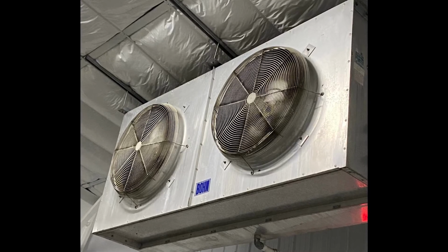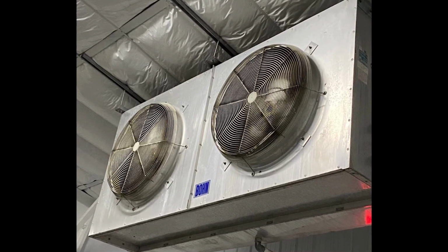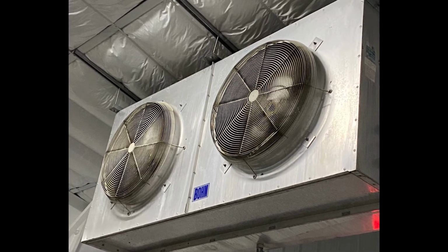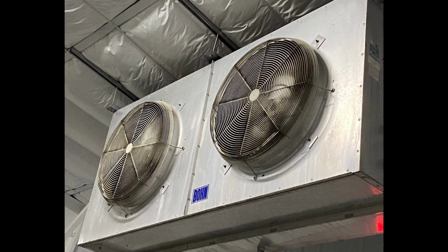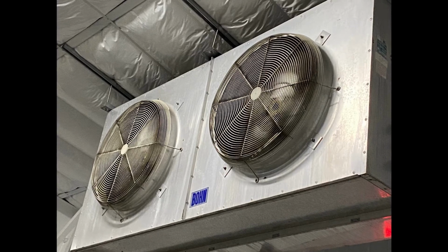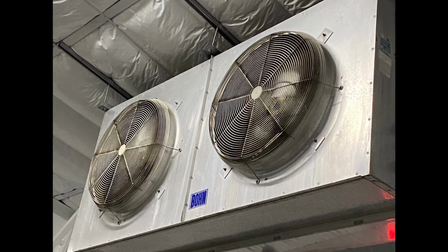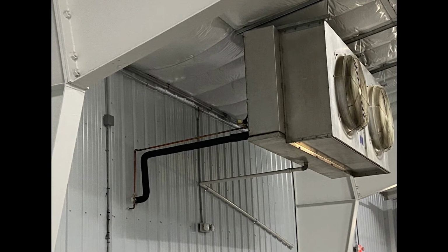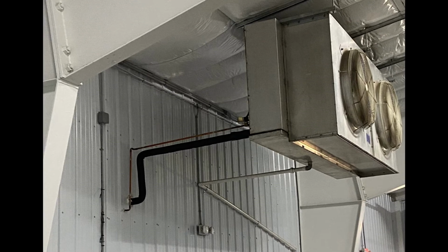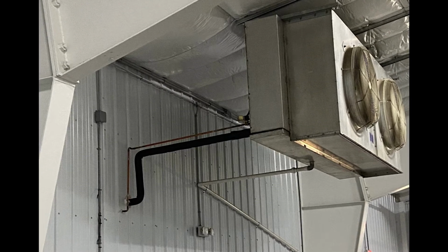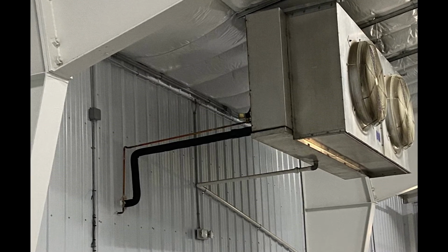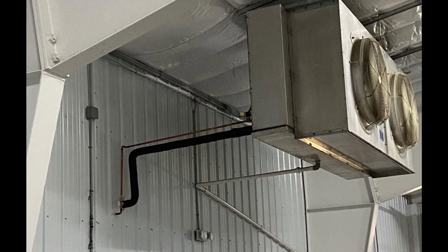Condensers and cooling units located inside the cooler are assessed during pre-operational sanitation inspection. Since the units distribute air throughout the entire space where eggs are located, it is essential they be maintained in a functional and clean manner. Water from condensation or defrost cycles may inadvertently drip onto eggs or egg packaging when these units malfunction. This is a major contamination concern and would be an unsatisfactory finding.